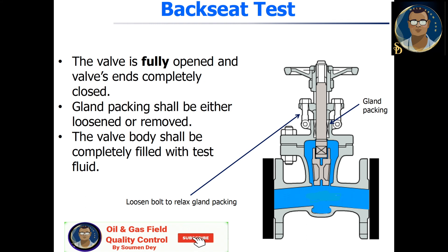Back seat test: the valve is fully opened and valve ends completely closed. Gland packing shall be either loosened or removed. The valve body shall be completely filled with test fluid.